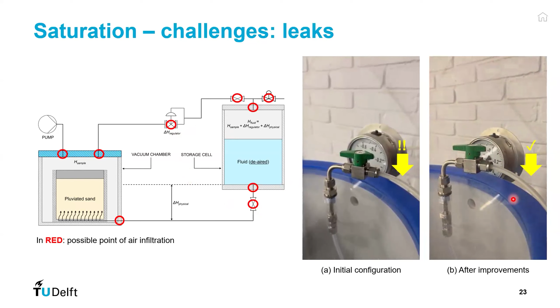Now, the solution is quite trivial, and it basically involves checking all of the connection points and also checking all of the valves. And indeed, we found that some of these connection points were leaking, and also we had 1 or 2 faulty valves in our system. After replacing those, eventually we ended up with the system that is shown in figure B. And what you can see is essentially that the fluid is completely free of air. This is exactly what you want for this kind of system.